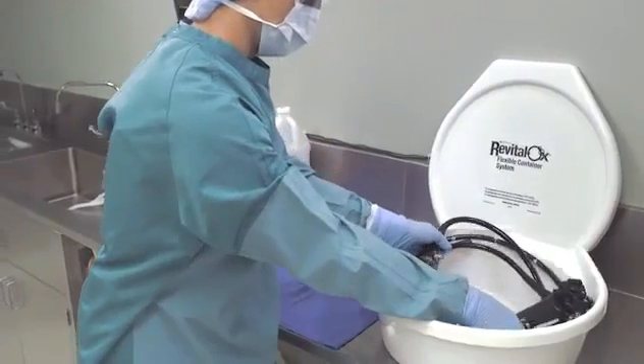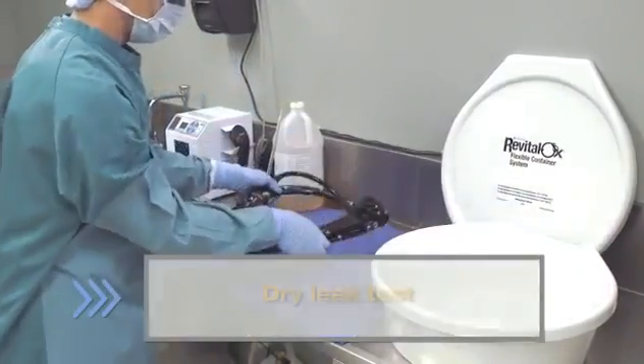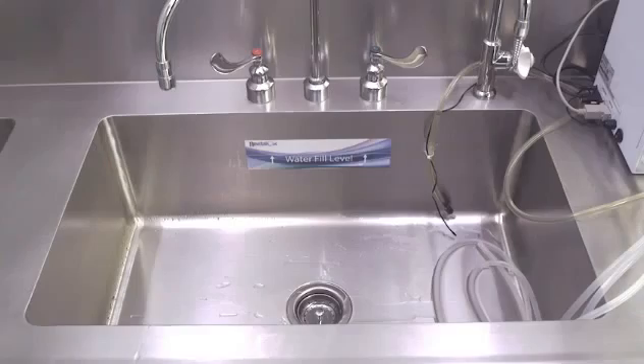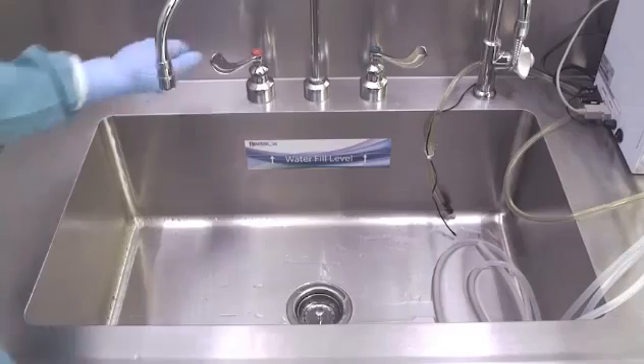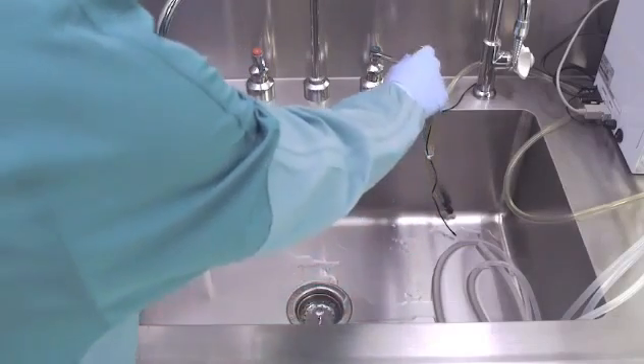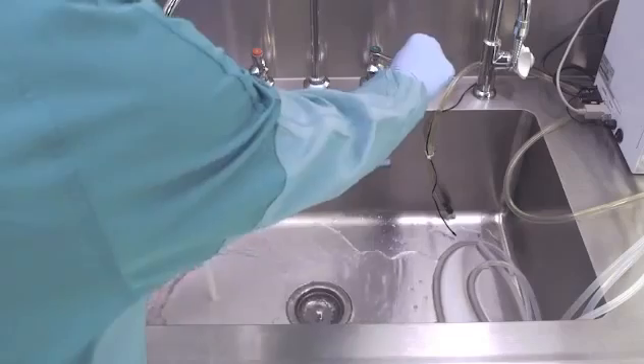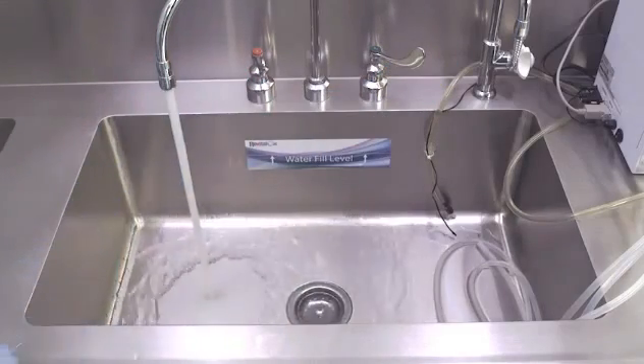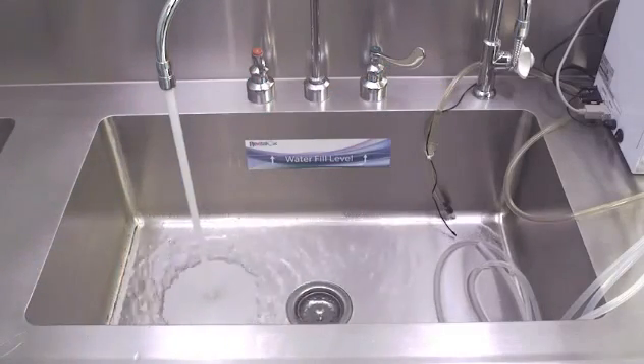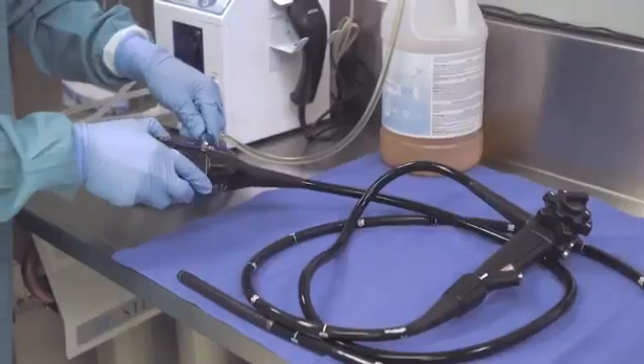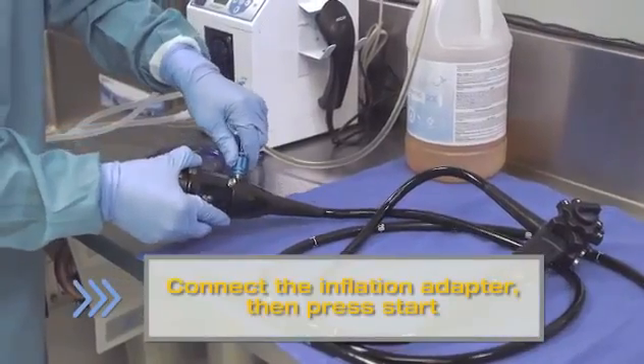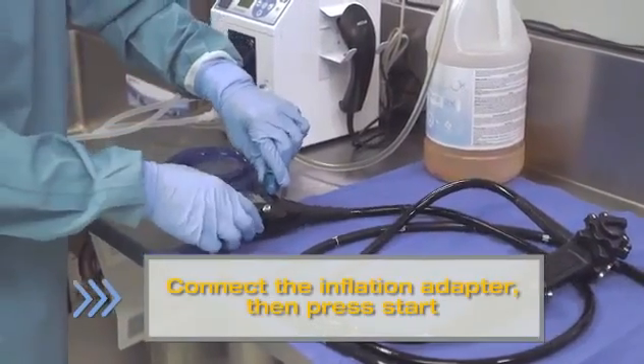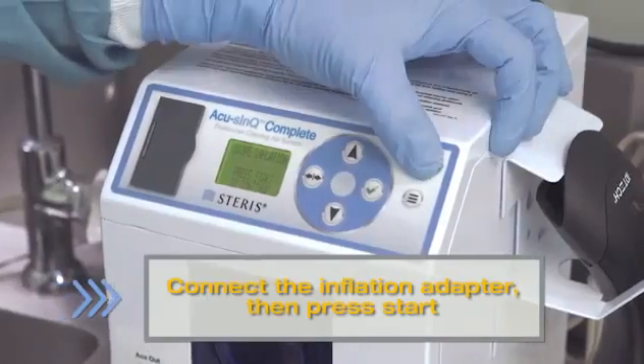After selecting the tech and scope, you are ready to perform the leak test. To maximize productivity, begin filling the sink that you will use later for the immersion leak test. Note: fill with water in the temperature range recommended by the IFU for the most efficient process. Connect the inflation adapter to the venting connector and press Start to pressurize the scope.